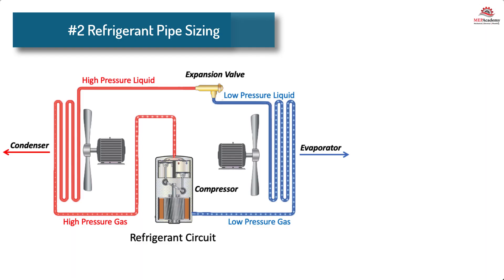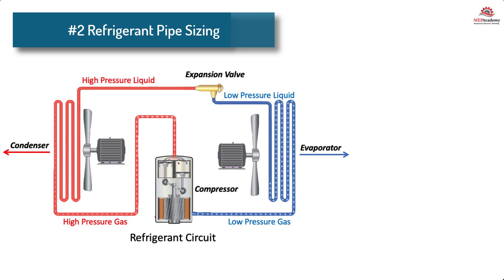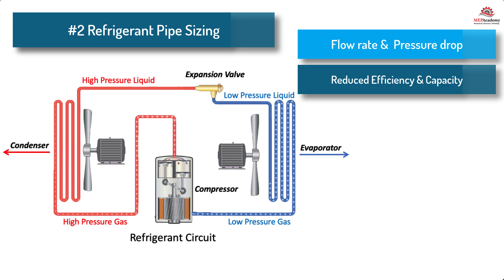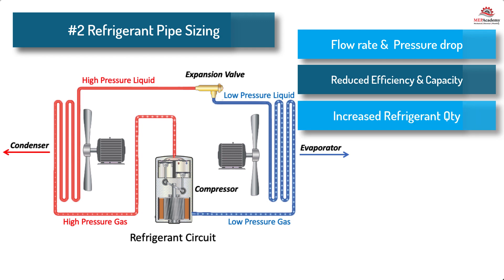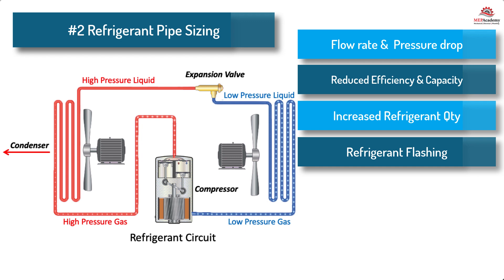2. Refrigerant pipe sizing. The diameter of the piping should be chosen based on the required refrigerant flow rate and pressure drop. The wrong size piping can cause excessive pressure drops, leading to reduced system efficiency and capacity while increasing power consumption. Liquid lines installed larger than required will increase the amount of refrigerant in the system, which could create additional problems. Undersizing liquid lines can cause the refrigerant to flash before it reaches the expansion valve, which will starve the evaporator and cause a loss in capacity and possible frosting up of the coil. If the suction line is oversized, there could be problems with the return of oil to the compressor, and if undersized, there can be a loss of capacity and an increase in superheat.